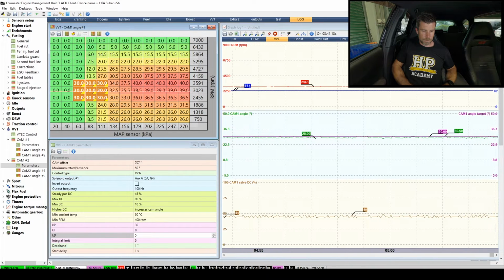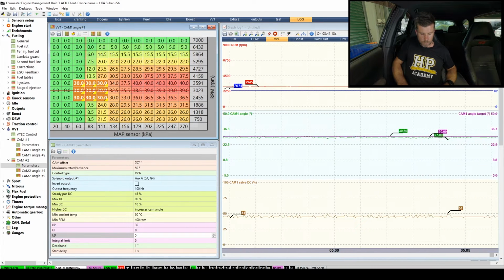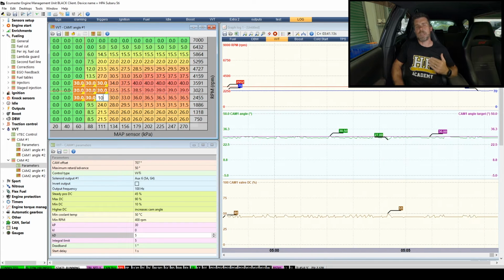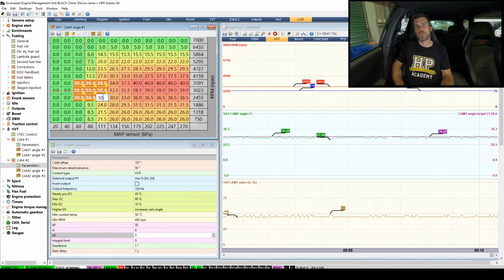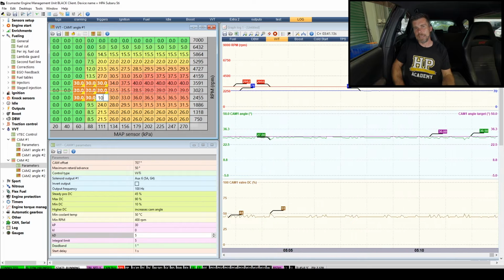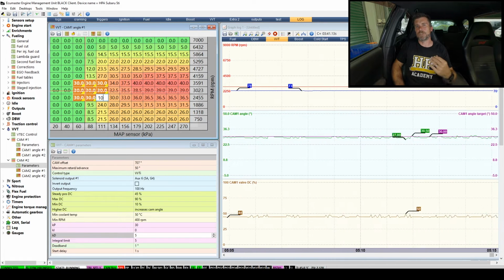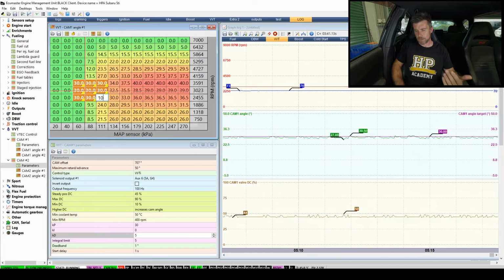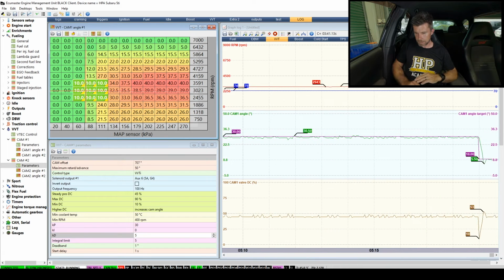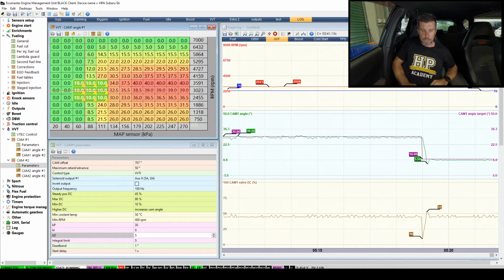So what we're going to do is make our step change again. We're going to enter a value of 10, and what we want to do is just analyze what happens when we get that first change. Are we going to still get that overshoot and oscillation? So let's press enter and see what we get. Alright, so that's actually looking pretty good there.